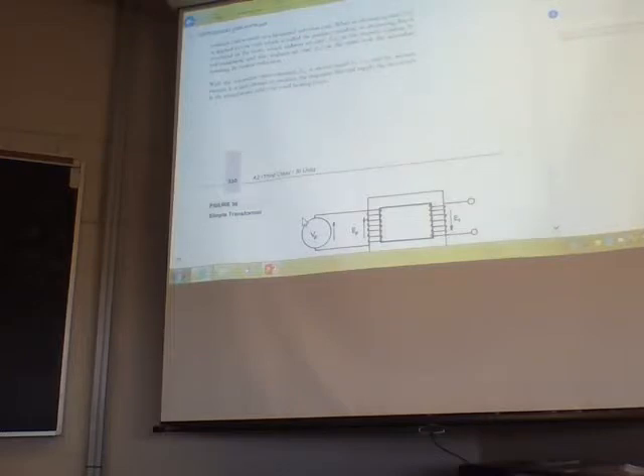Transformers are efficient. All you get is heat losses. Any transformer that you see is energized, there will be some heat. In a transformer, it can be assumed that all the flux produced by the primary cuts every turn of both the primary and secondary winding, thereby inducing the same voltage in every turn.